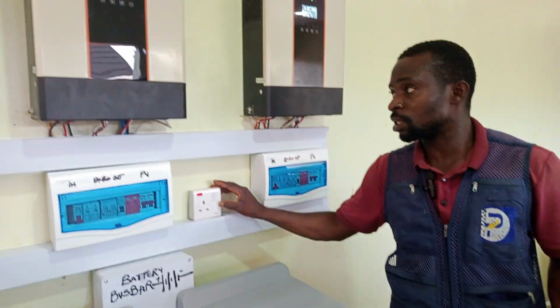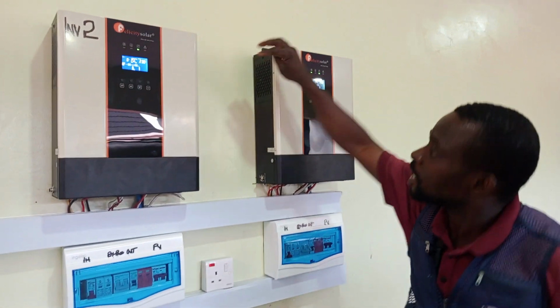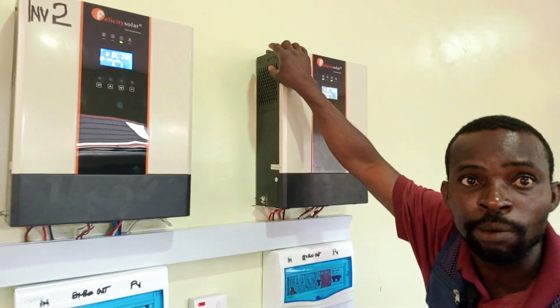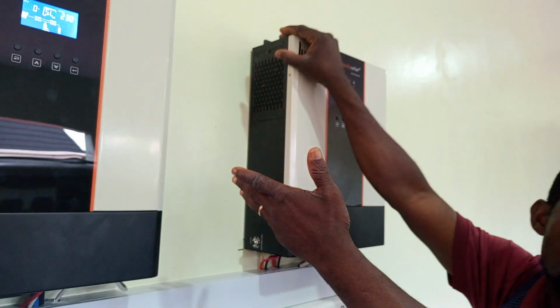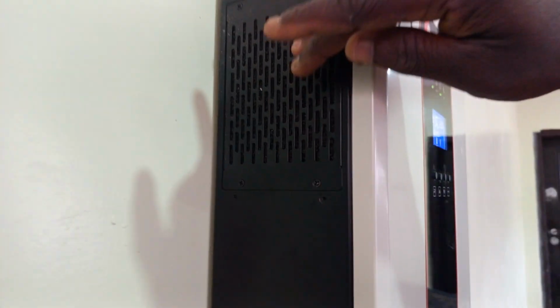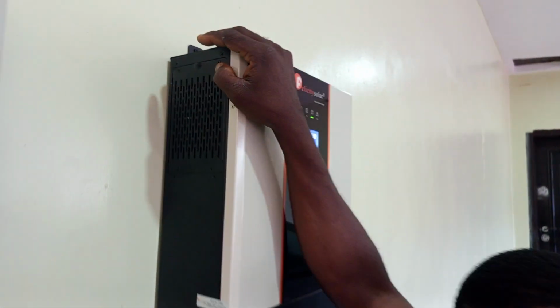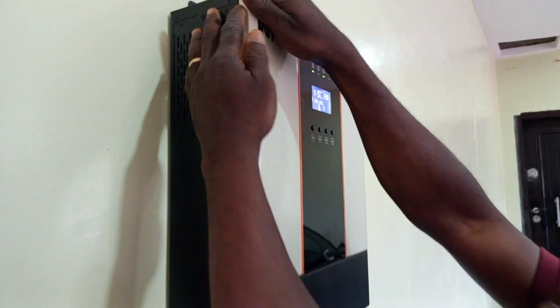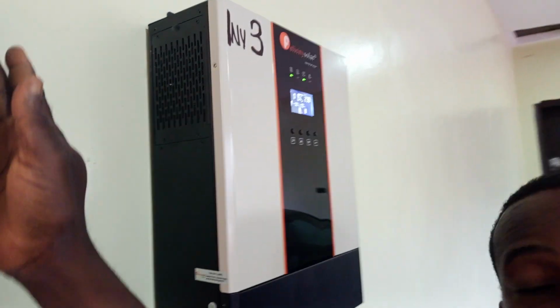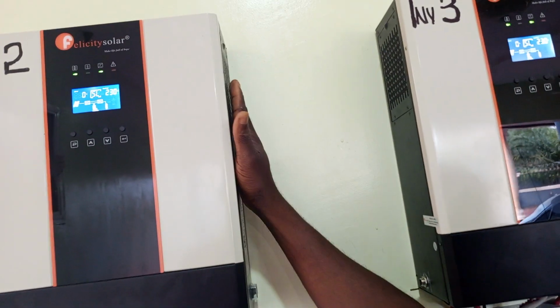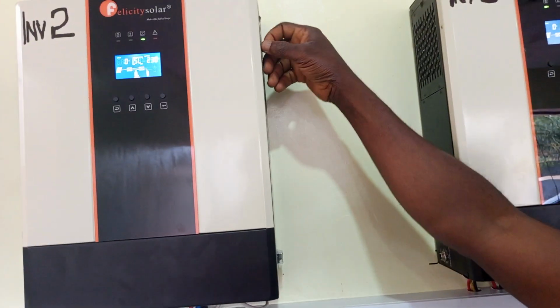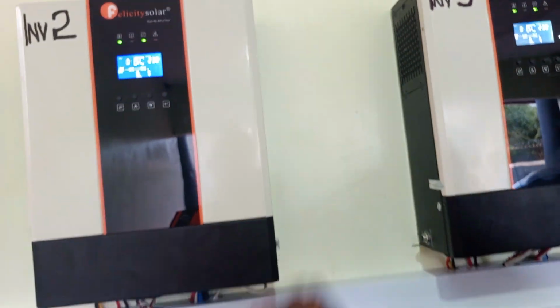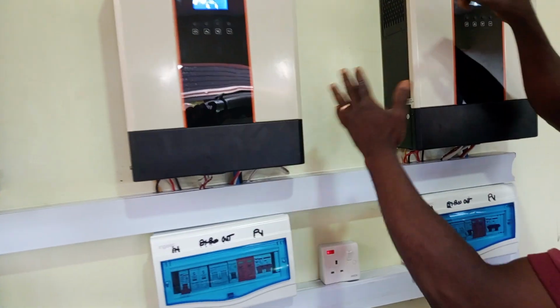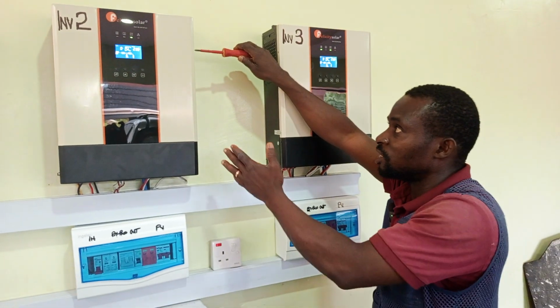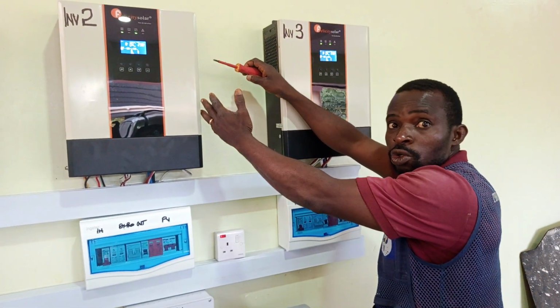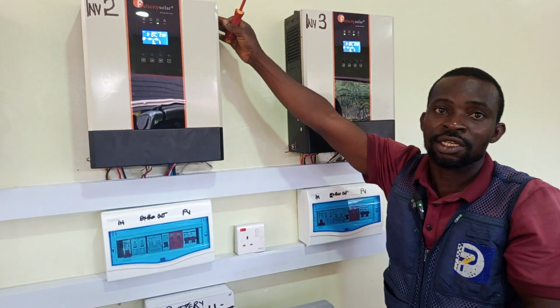Let's assume you want to carry out maintenance. On this side of the inverter, there's a filter. You just have to use your blower to dust it, maybe once every 6 months or once a year. Come with your blower, loosen this screw with your screwdriver. If you are installing more than one inverter, make sure you leave a distance so you can access and loosen the screws, because if they are too close together, you cannot access this filter.